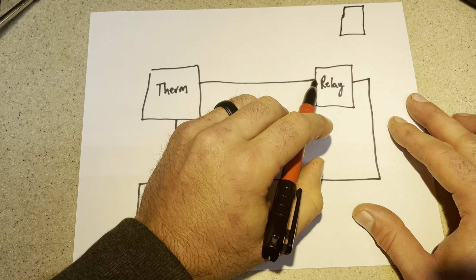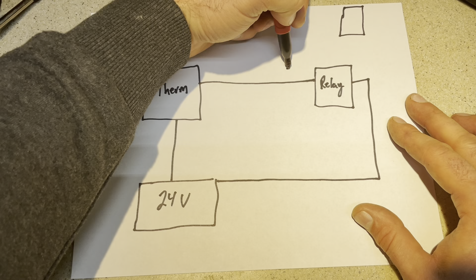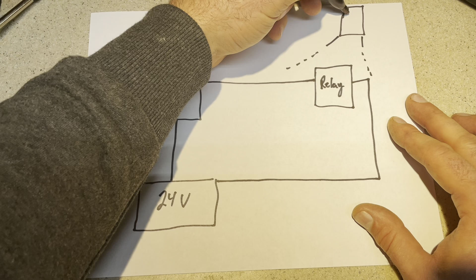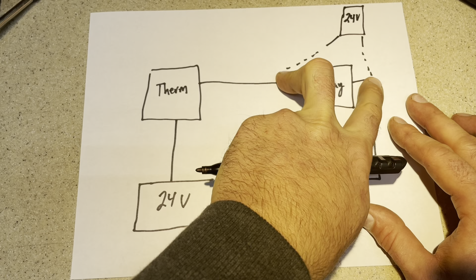So you get your meter, you unplug the wires, and you bring them up to your meter, hook in, and you see 24 volts between this wire and that wire. It's a bad relay, right?